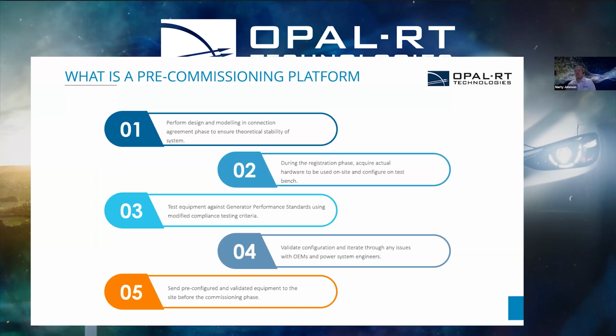And then once we've got that, we'd test that equipment against what in Australia we call the generator performance standards, but effectively it's just the set of rules that a generator has to comply with when connected to the NEM. We would do this to mimic the same kind of testing that we would do on site. Once we validate this performance and benchmark it against our models, we fix any issues that come up, and then we take this equipment that we've already pre-configured and validated and send it straight off to site before commissioning happens.